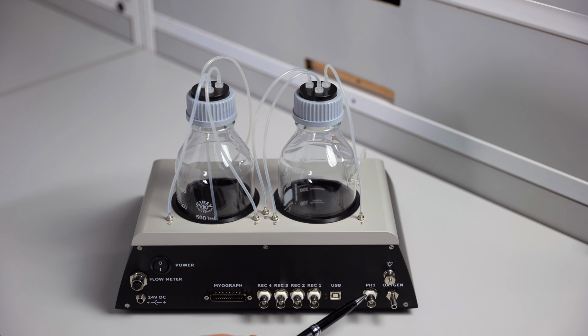This is a connection for an optional pH meter. This port is for the oxygen or gas tank, which will exert pressures and flow in your system. And finally, there is a grounding port to eliminate any electrical noise.